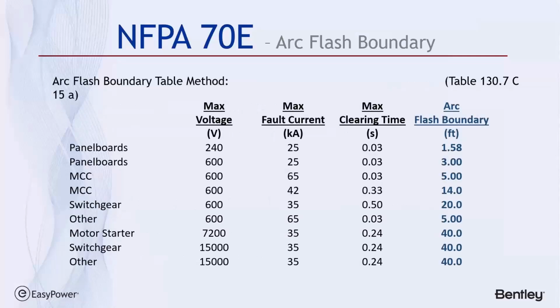In NFPA 70E, there is Table 130.7(C) that describes a listing of different types of equipment, in this case panelboards up through switchgear at different voltages. If we know the maximum current and the clearing time, then they give us the arc flash boundary that should be respected when that particular bus is exposed. Now the caveat, or the catch-22, is if I don't know what the max current is or the clearing time, how do I find it? Well, you find it by doing an incident energy analysis, in which case you cannot use this table.